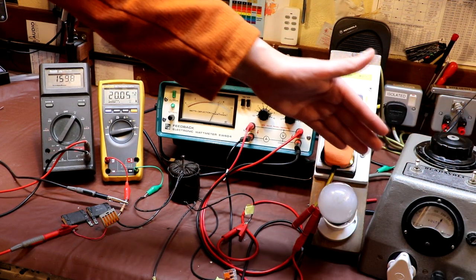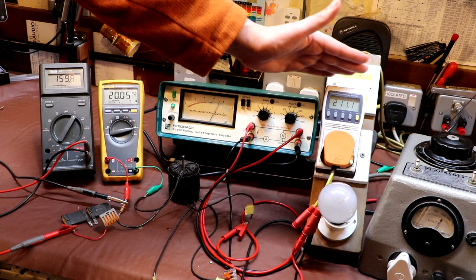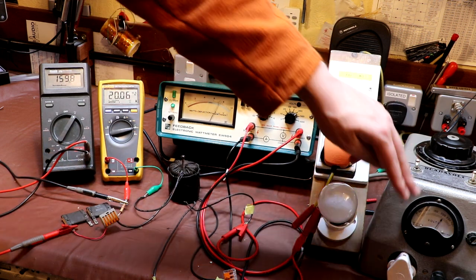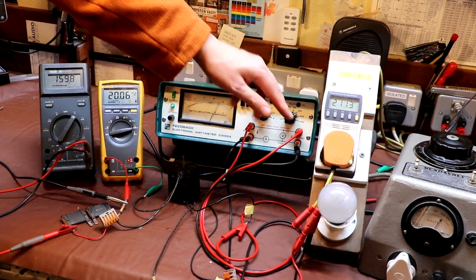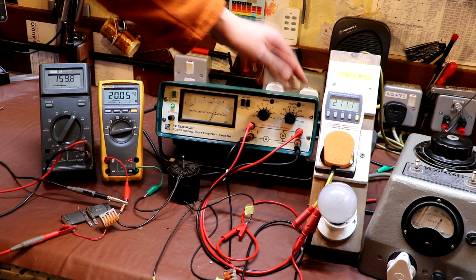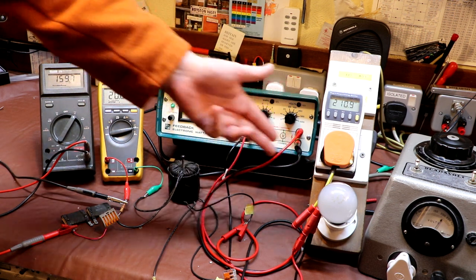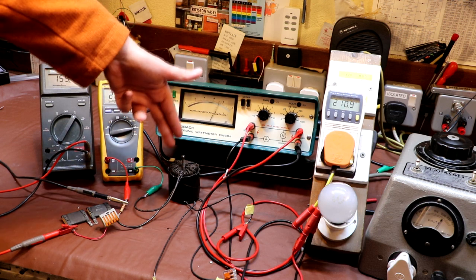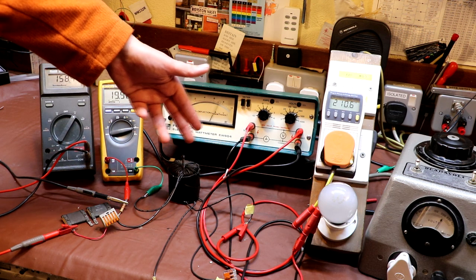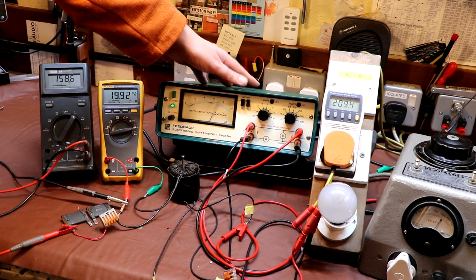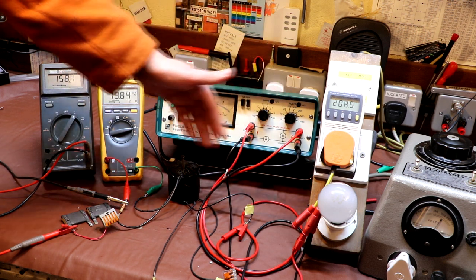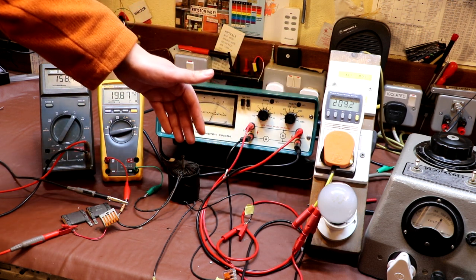So the power's coming from the variac, it's going through here, which is measuring the voltage because it's more accurate than the meter on the variac, and then that power is going into the watt meter here. So it goes into one side of the watt meter and comes out at the other side, and it goes into the primary of the transformer. So again, all our watt meter is doing is measuring the total power which is being supplied to this transformer.